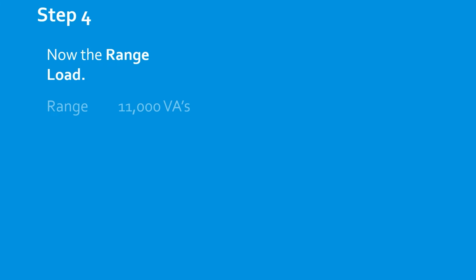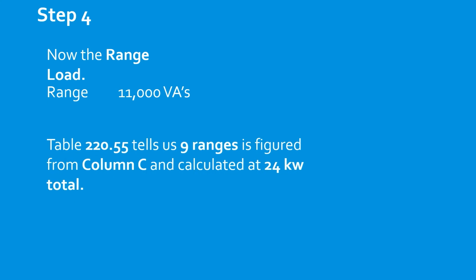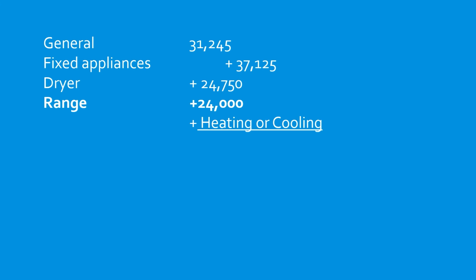Now the range load. Our range is 11,000 VAs. Table 220.55 tells us 9 ranges from column C. That total calculated load is going to be 24 kW, which is 24,000 VAs. So we just add that to our calculation.